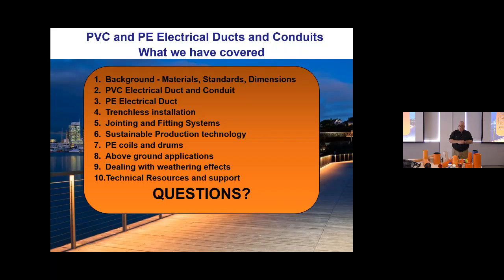Now, if you look at the pricing of the polyethylene fittings, they're probably quite much more expensive than the PVC ones because they're so complicated and use so much material. No, not really. I mean, a joint is what it is. So the alternative with polyethylene to a fitting like that is to use an electrofusion coupling, for which you require a fitting, an electrofusion control box, a source of electricity, and all of the preparation and rerounding clamps that go with it. Whereas with this, you just trot onto site with a couple of wrenches and just join it.